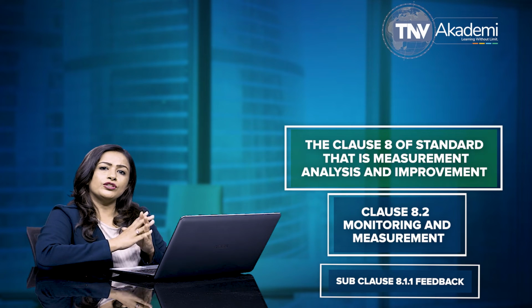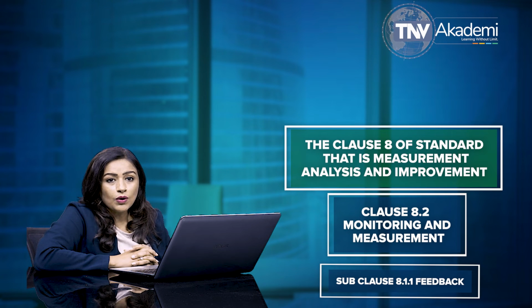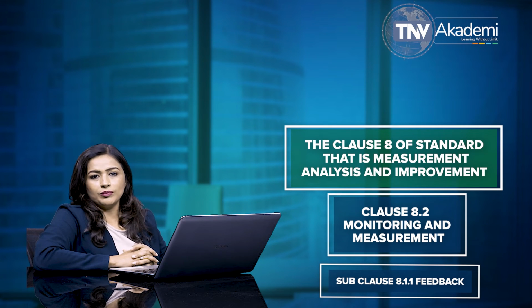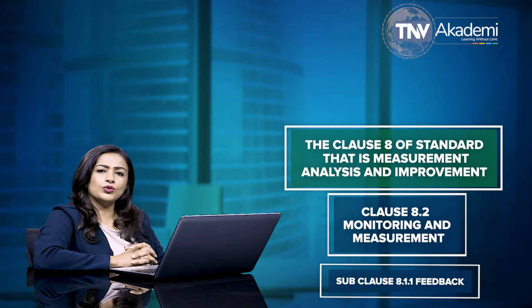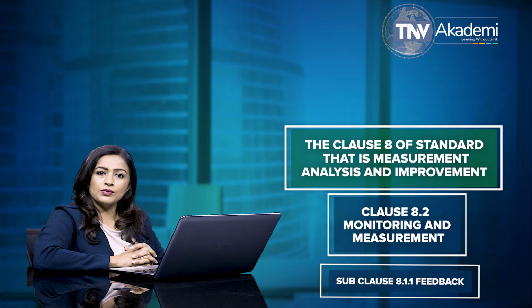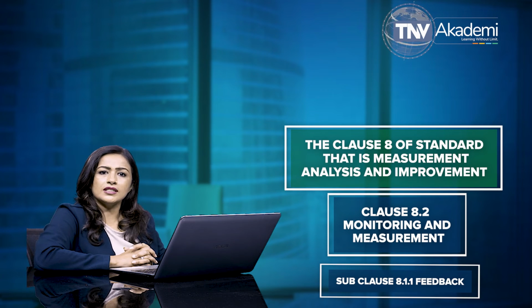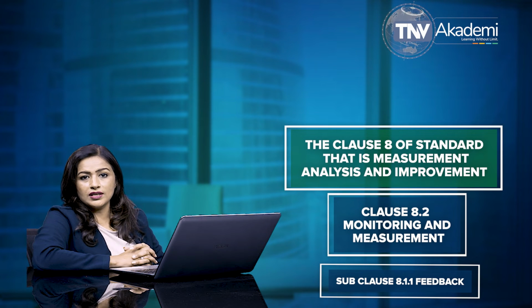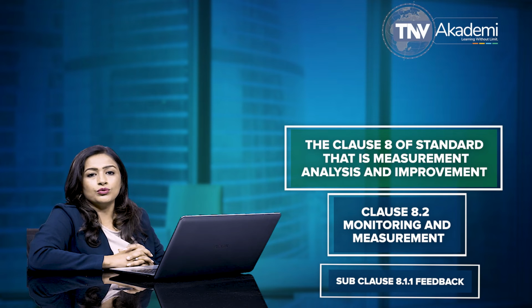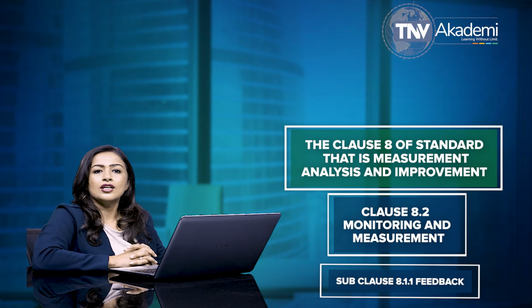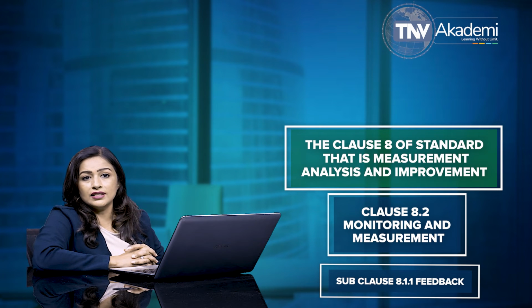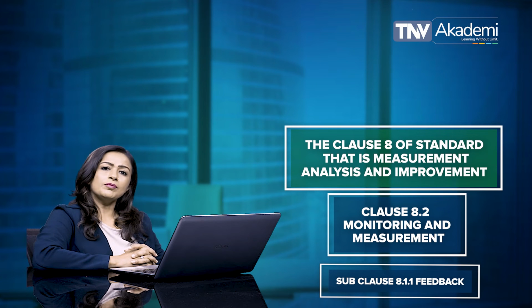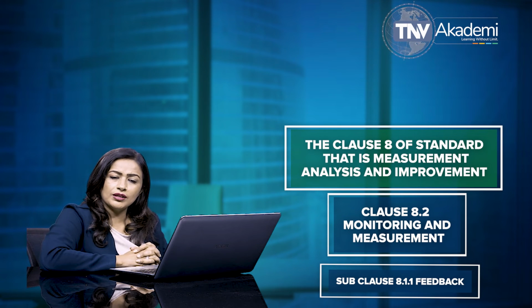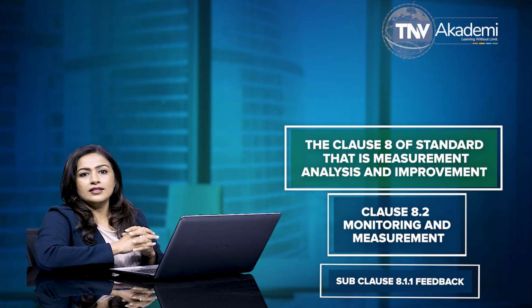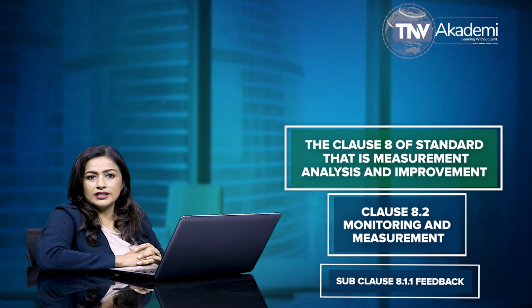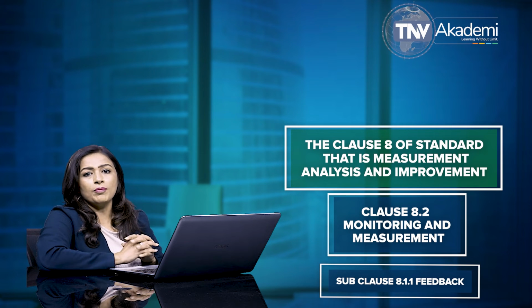The subclause 8.2.1 states that the organization is required to document procedures for the feedback process. This feedback process must include provisions to gather data from production as well as post-production activities. According to this subclause, the information gathered in the feedback process must serve as potential input into risk management for monitoring and maintaining the product requirements as well as the product realization or improvement processes. The subclause further states that if applicable regulatory requirements require the organization to gain specific experience from post-production activities, the review of this experience must form part of the feedback process.